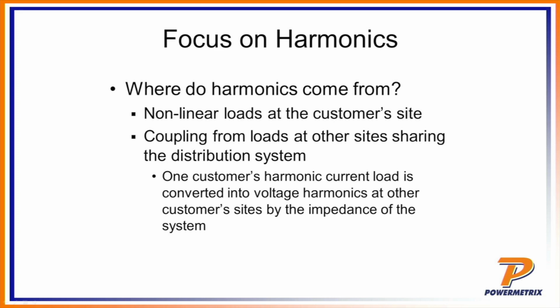Moving on with harmonics. Where do the harmonics come from? Harmonics once again come from nonlinear loads at a customer's site. That could be a variety of different things. It could be something as simple as the lighting. Here in a moment we're going to look at different kinds of lighting and what sort of harmonics are being generated from that. It could be something like, say, an arc welder, something that draws a large transient of current on a momentary basis, on a periodic basis at very small moments in time.